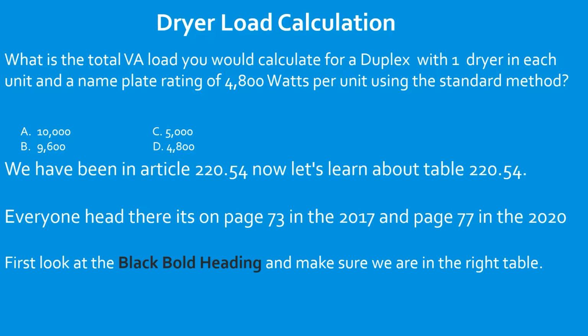So on the left-hand side is the number of dryers. That's pretty simple. Now let's look at the other black bold heading. Go over to the next column to the right, and it says demand factor, and it's in percentages. Remember, we learned previously that demand factors are either increasing the demand or decreasing the demand that you have to calculate for your load calculation. So let's say you had 6 dryers. When you go over there and tee off, it says 75%. So whatever your load was, you would just multiply by 0.75, and that would ultimately give you the demand that you would use for your calculation.